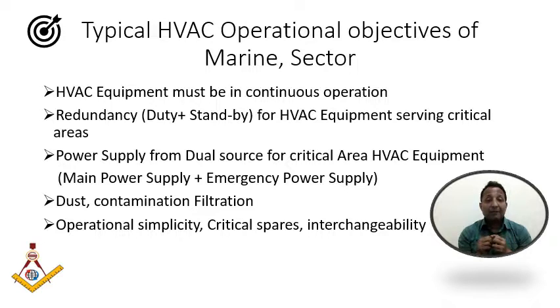In case a fire happens, the HVAC system gets shut down because it is a major source of spreading fire, since it supplies oxygen in large quantity, and of course if fire is happening nobody is going to stay there, so what's the point in starting the HVAC there? But you still have a staircase and you need to pressurize it. Imagine the main power source is off - then you need to provide emergency power to the staircase pressurization fan. So we need to identify which areas are critical like this and plan our power source accordingly. This is how HVAC also plans the emergency power.